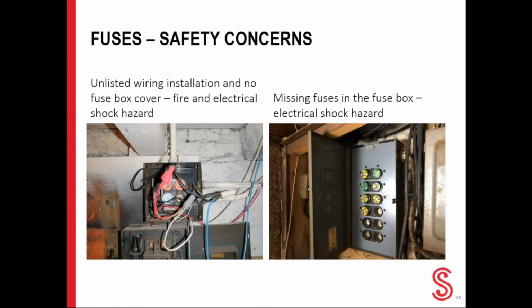So with these fuses also come safety concerns. If you use a fuse that's too large for the application, let's say you go with a 60 amp fuse when it's supposed to be a 20 amp fuse, that creates a significant fire hazard because the fuse would no longer stop the flow of electricity when it was required. So some people, and you may have seen this, have even used copper pennies in place of a fuse or a metal bolt or something else. And of course, this provides no protection at all, and it really shows the vulnerability of this type of system.